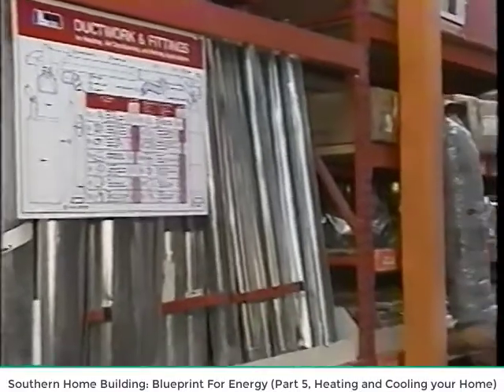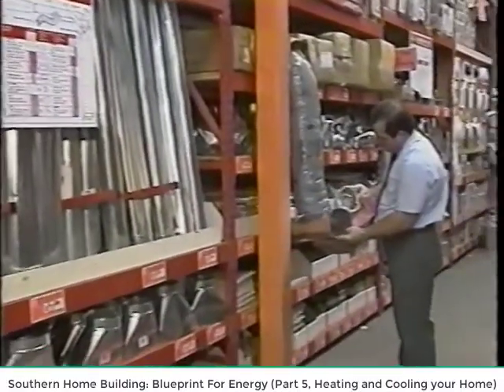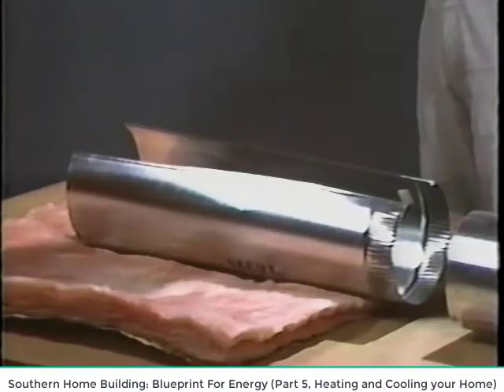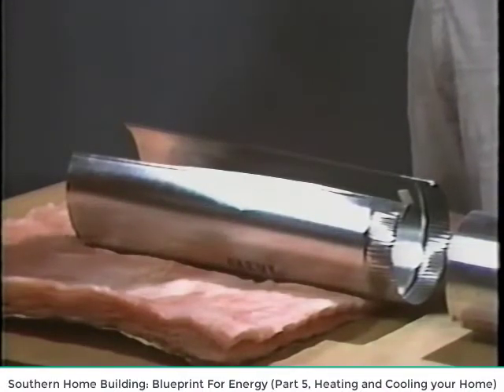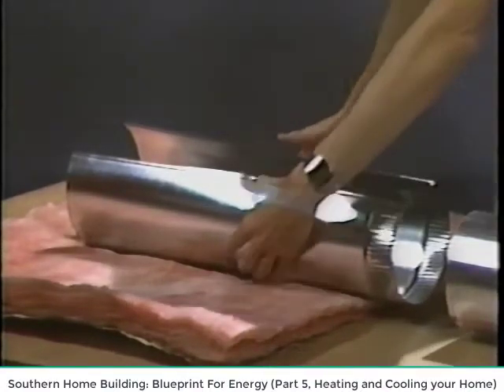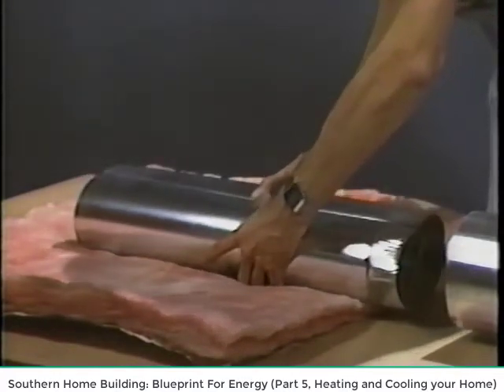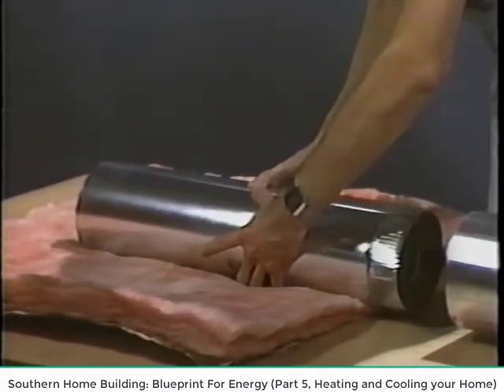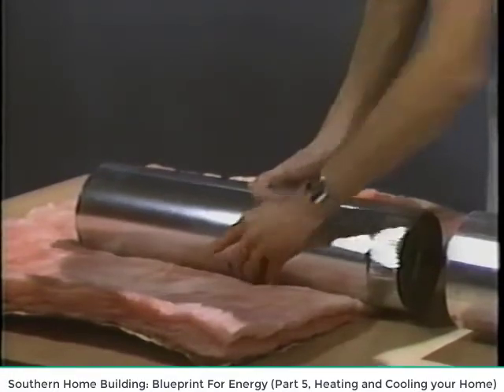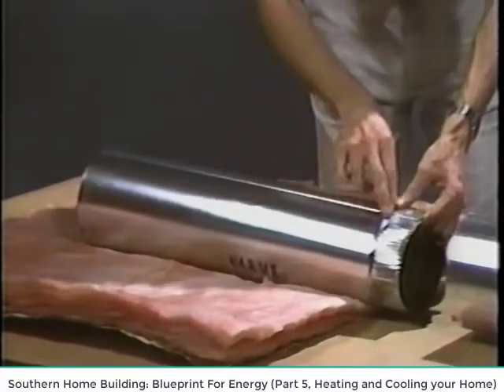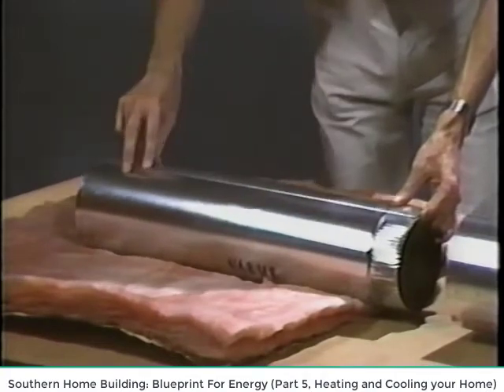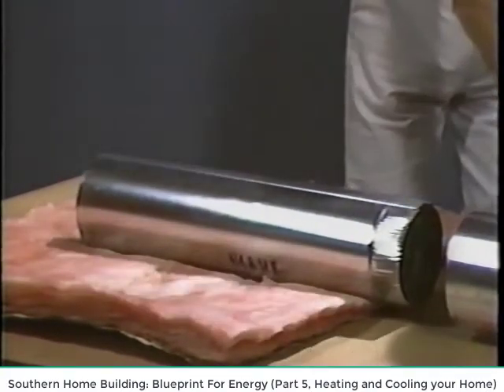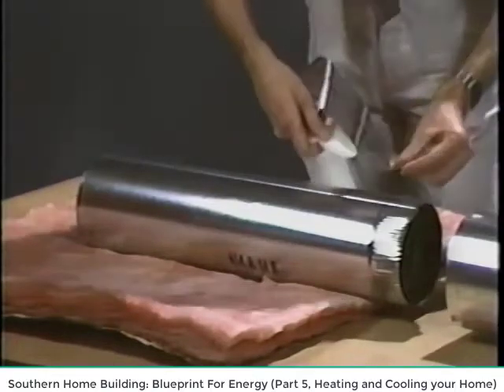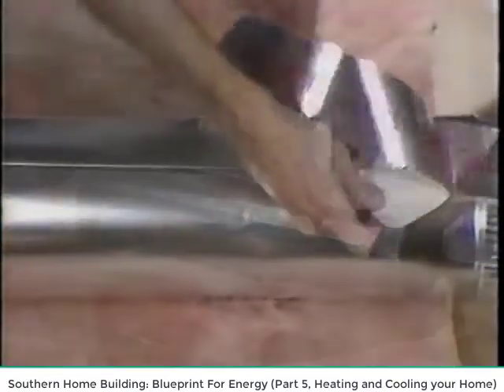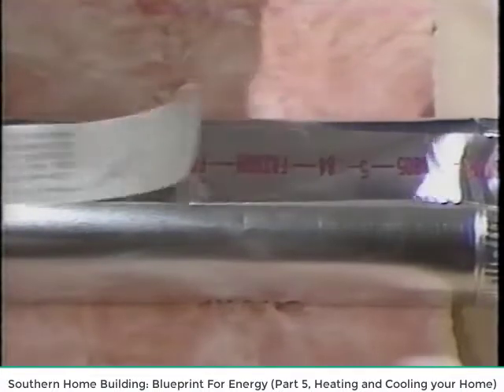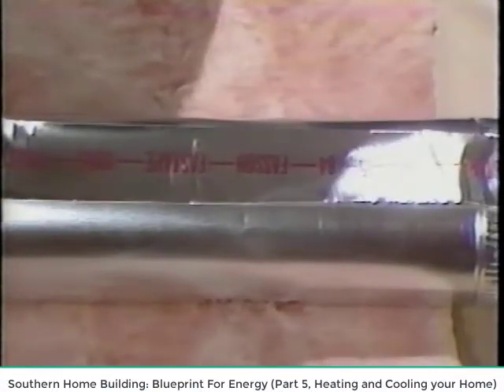Homeowners face another choice when selecting the type of duct to be used. Three types of duct are commonly used: round metal duct, fiberglass duct board, and flexible plastic duct. Round metal duct has several advantages. It is very smooth, so it minimizes air pressure loss and allows smaller diameter duct to be used. No mildew or fungus can grow inside the galvanized, zinc-coated surface, and if the joints are taped properly with the best quality foil tape, it can be made very airtight.